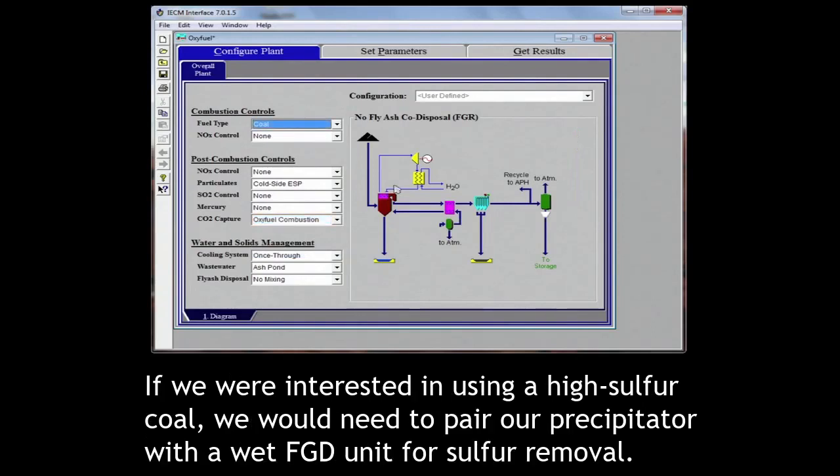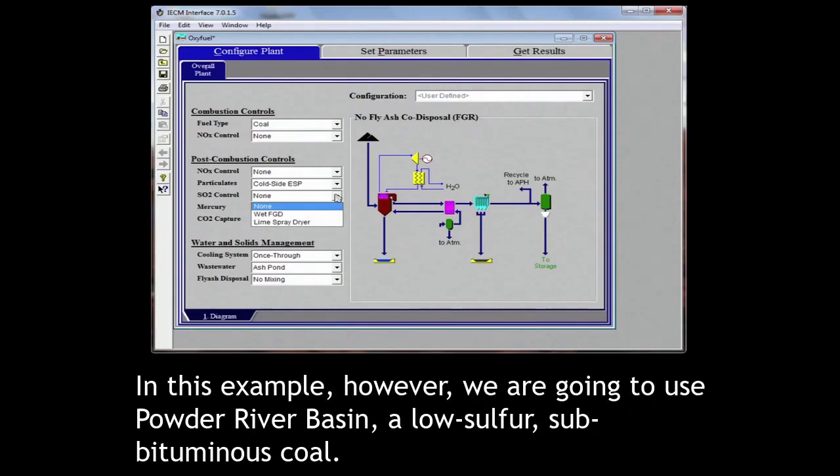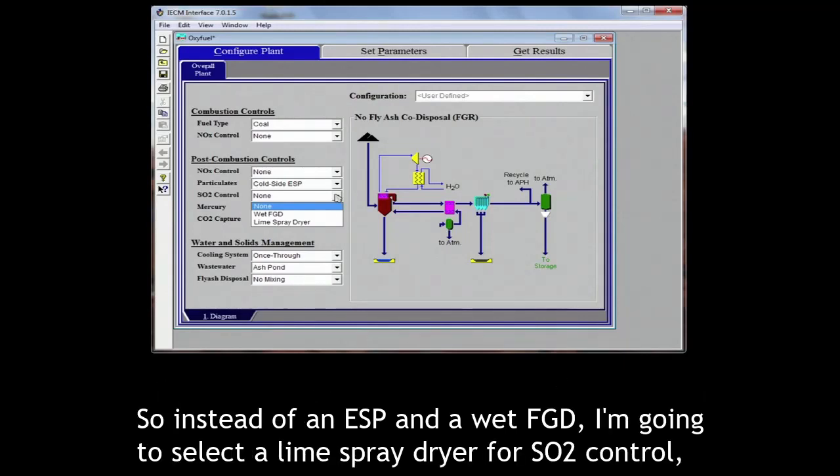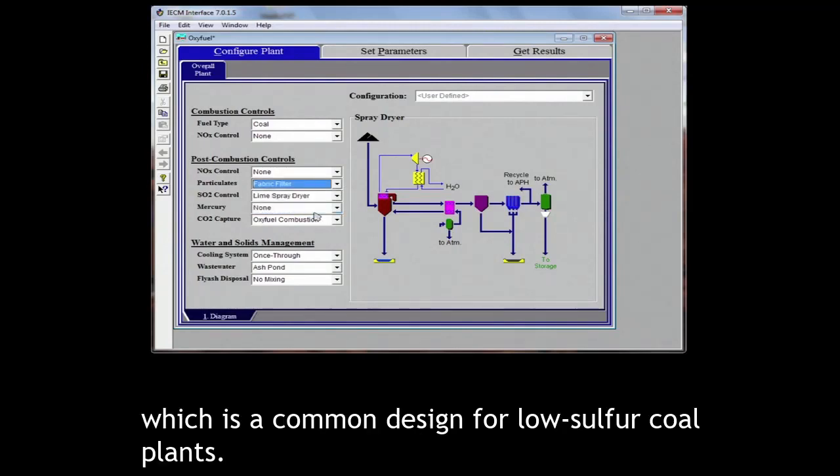If we were interested in using a high sulfur coal, we would need to pair our precipitator with a wet FGD unit for sulfur removal. In this example, however, we are going to use Powder River Basin, a low sulfur subbituminous coal. So instead of an ESP and wet FGD, I'm going to select a lime spray dryer for SO2 control and a fabric filter bag house for particulate collection, which is a common design for low sulfur coal plants.